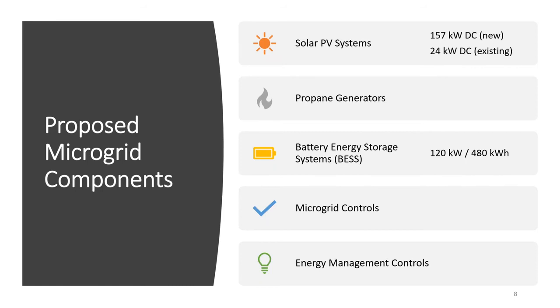In addition to providing backup power, when the system is grid connected—this is a grid-tied microgrid—it also provides energy cost savings through energy arbitrage, buying power at low prices and storing it to deploy during peak price periods, and also through offsetting demand charges, or demand charge reduction. So those are all tied together.